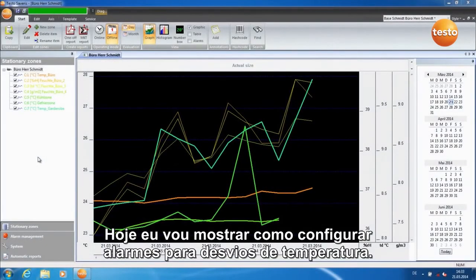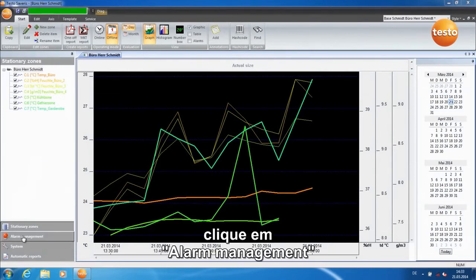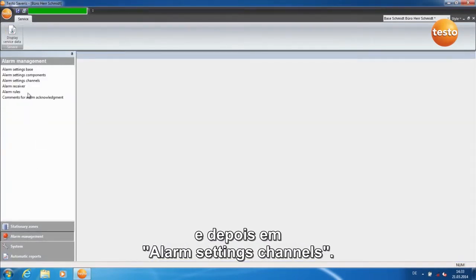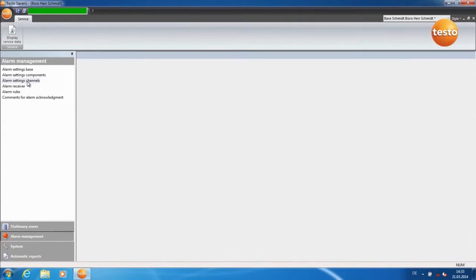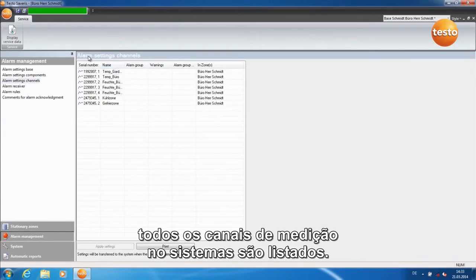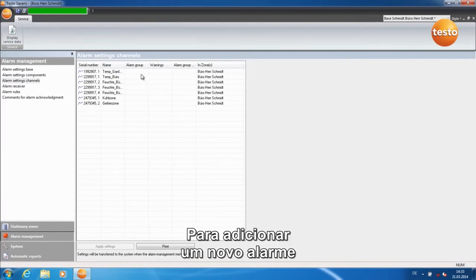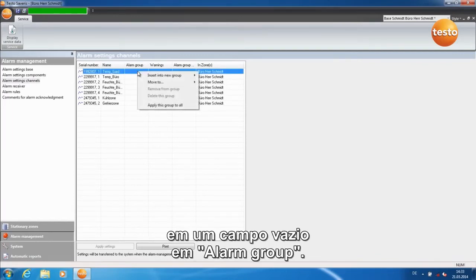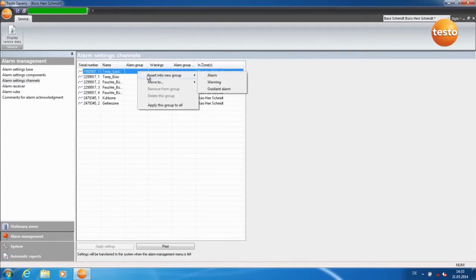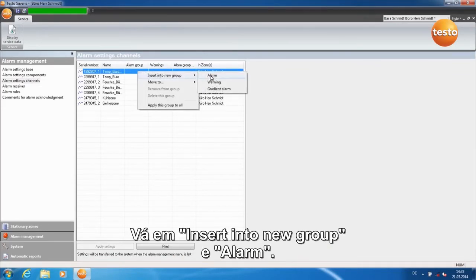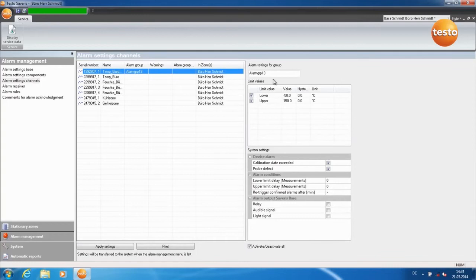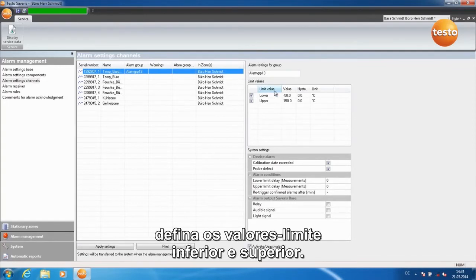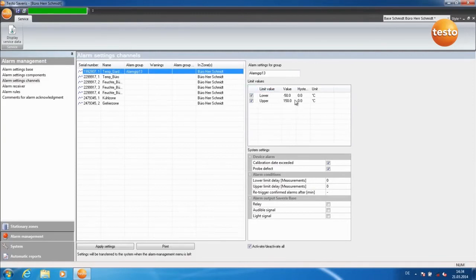Today I'm going to show you how to configure alarms for temperature deviations. To do this, click on Alarm Management and then on Alarm Settings Channels. In the table in the middle, all measurement channels in the systems are listed. In order to add a new alarm, click with the right mouse key into an empty field under Alarm Group. Go to Insert into New Group and Alarm. Name your alarm group. For limit values, define upper and lower limit values.